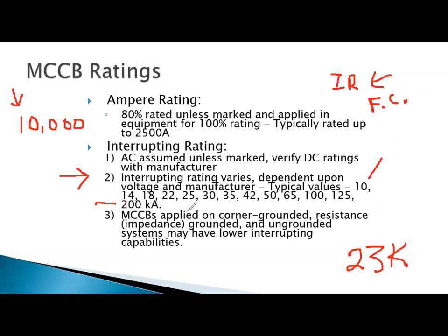And so I don't really want to go with 25. That's kind of close. I think I'll go with 30,000 amps. Because here's what happens if that interrupting rating is lower than the available fault current. The circuit breaker or fuse will explode, and it's going to sound like three sticks of dynamite just went off. And that has happened in many facilities, right? We just did not pay attention to the interrupting ratings.